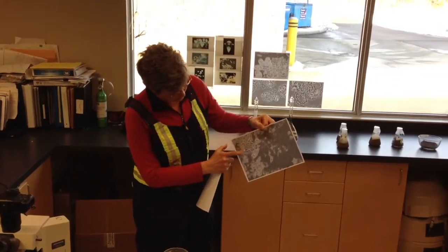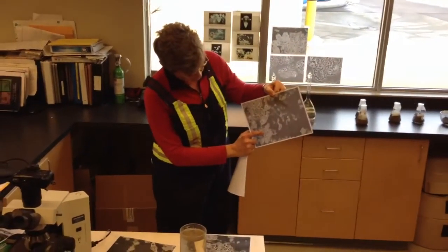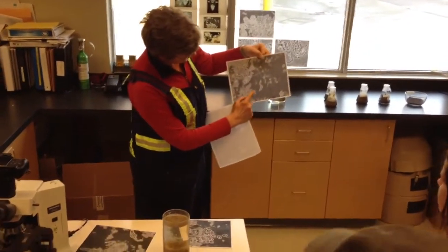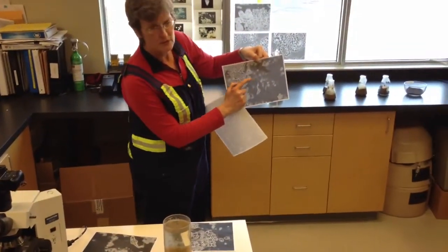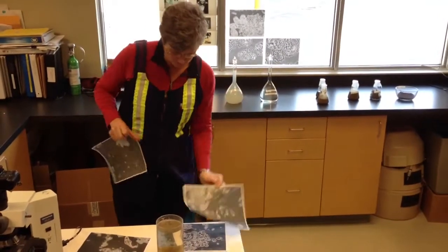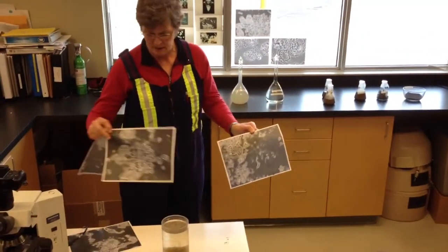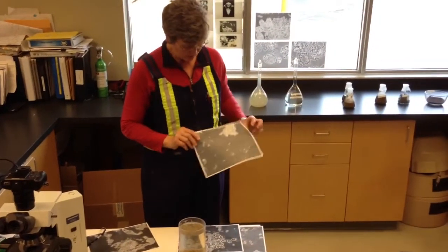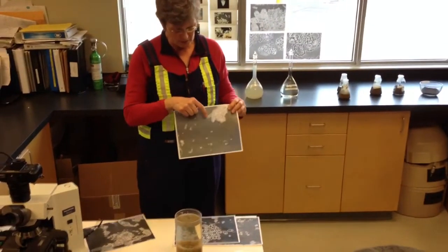These are the animals that are eating the bacteria, but the bacteria are really these flocculating kind of bacteria that clump, and then bacteria that grow in strings, filamentous bacteria. So these are some of the pictures I've taken off of our microscope. We want to have this kind of bacteria, the flocculating bacteria.